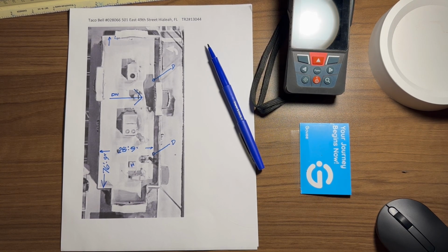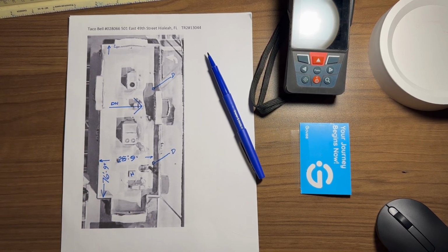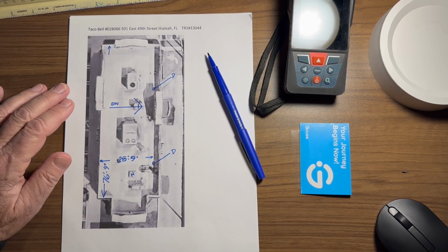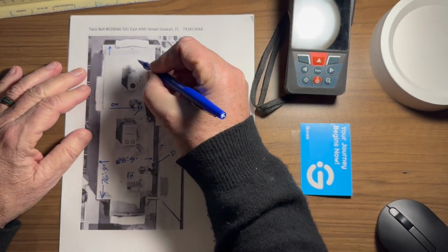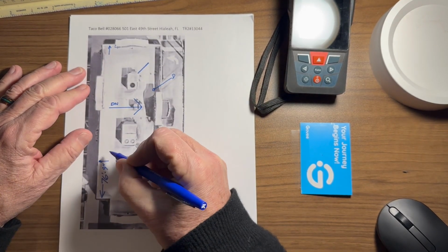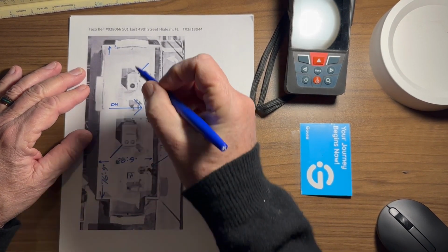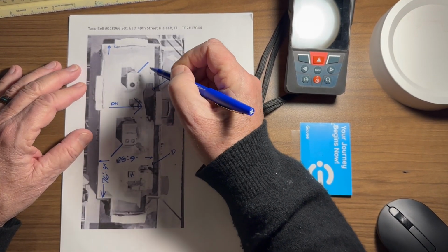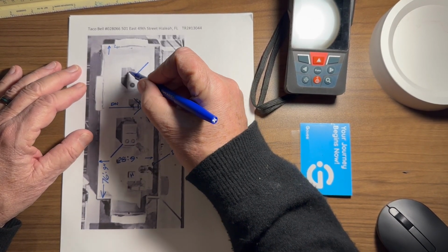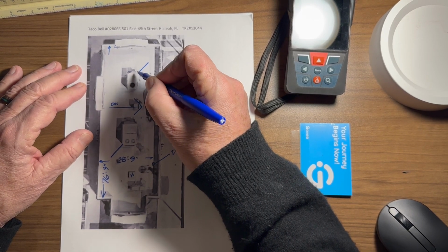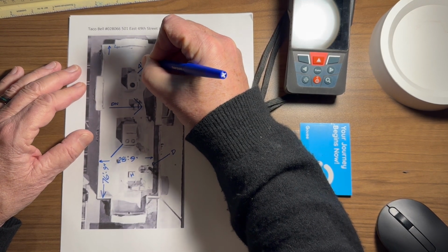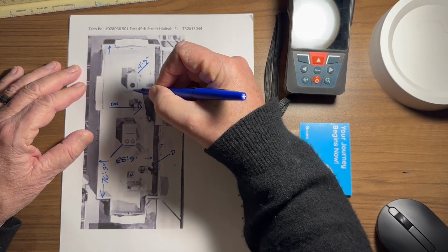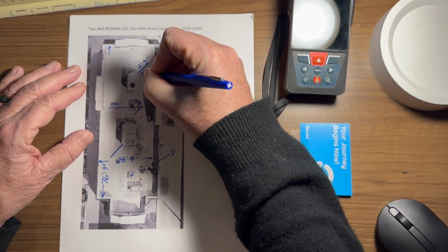The next thing we want to do is document the size of the RTU curbs and their exact locations. So for that, we use a tape measure, just a regular standard tape measure. We draw a diagonal line off of the unit. Any corner is fine, but we just use that line to give a way to organize the data. In this particular one, we measured from left to right here on the curb itself, and we got 4 foot 9 inches. And we measured up and down on the curb itself, and we got 7 foot 10 inches.